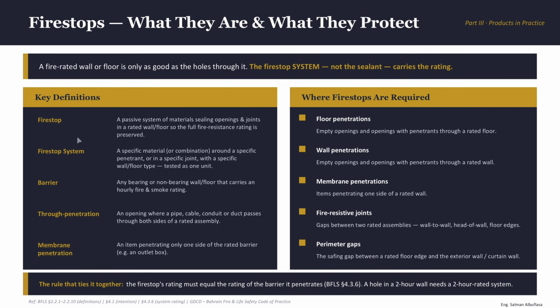And this is where firestop comes in. A firestop is a passive system of materials that seals an opening or a joint in a rated element, for example, that wall that has been drilled, so that the element keeps its full fire resistance rating as it was before. We drilled holes, and that's usual in every project. Now we need to reseal it again in the proper way.